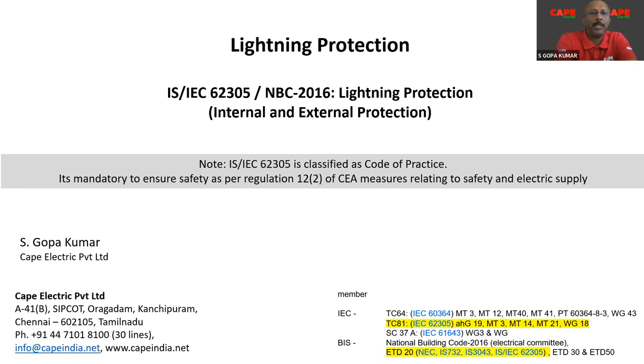The contents of the presentation are from IS IEC 62305, or you can also say from the National Building Code 2016, internal and external lightning protection. The first point which I wanted to tell you is that IS IEC 62305 is a classified code of practice. Code of practice is a little bit above the standard as per the regulation of the Government of India. Code of practice is a mandatory requirement which has to be implemented in every building. You can look at it in regulation 12.2 of CEA, measures relating to safety and electric supply. So basically, IS IEC 62305 is a code of practice. Similarly, National Building Code is also a code of practice.